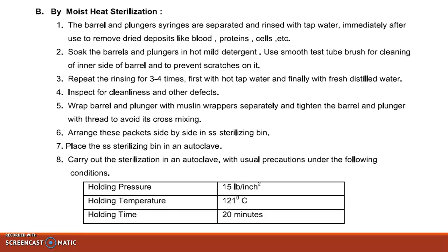Now you have to wrap the barrel and plunger with muslin wrapper separately and tie the barrel and plunger with a thread to avoid cross mixing. Now arrange these packets side by side in the sterilizing bin. Place the sterilizing bin in the autoclave. Now carry out sterilization in the autoclave with the usual precautions under the following conditions. The conditions we are going to maintain in the autoclave are holding pressure 15 pounds per square inch, holding temperature 121 degrees Celsius and holding time 20 minutes.